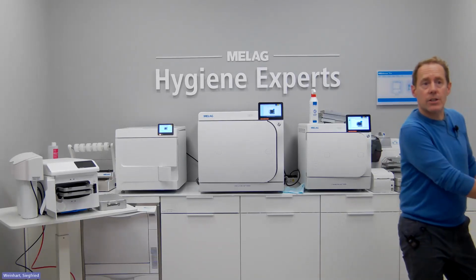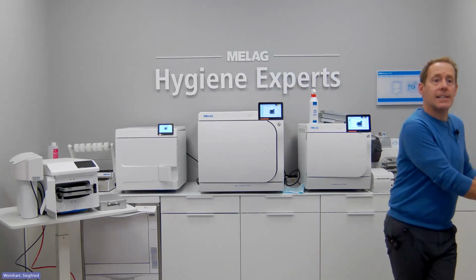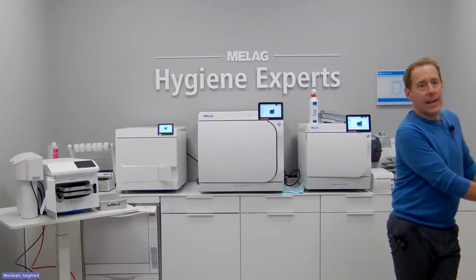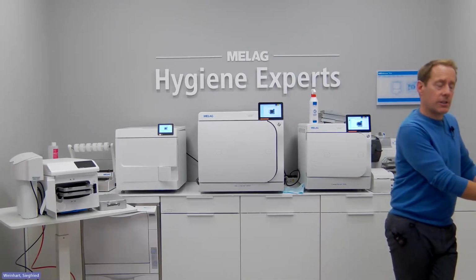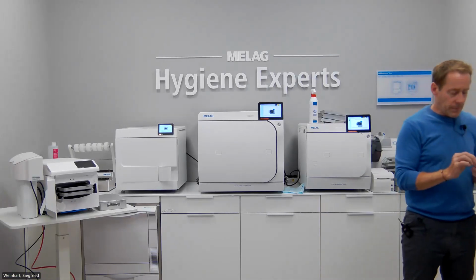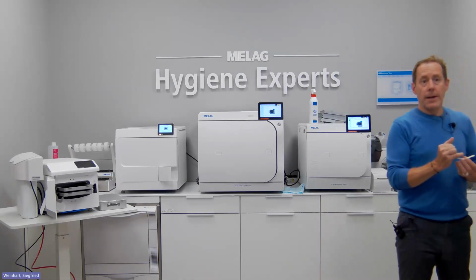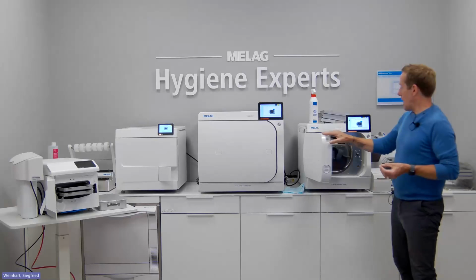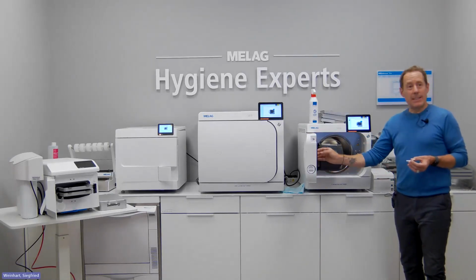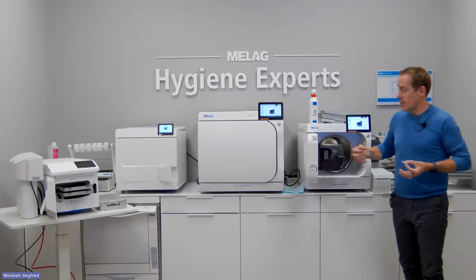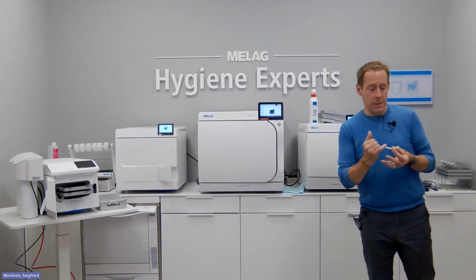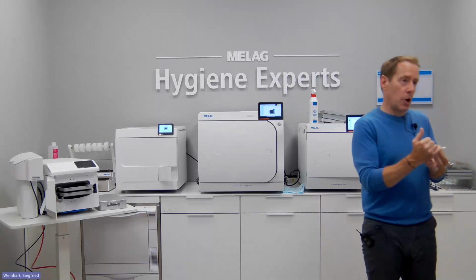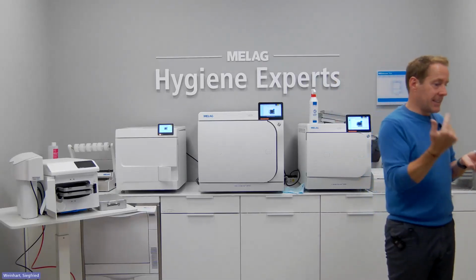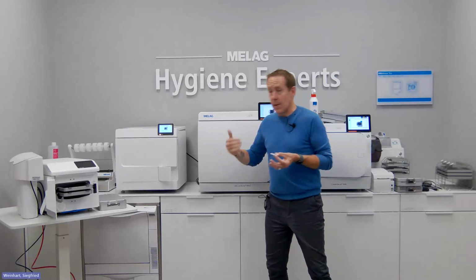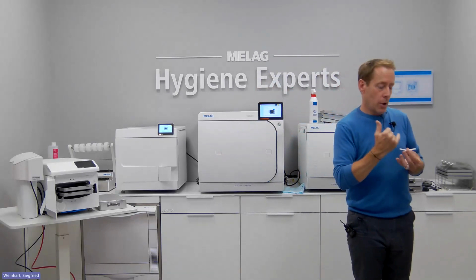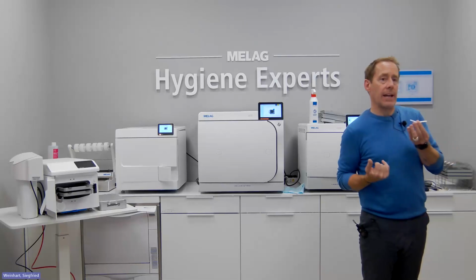If a helix doesn't change color completely, but does change partially, is that okay? No, it's got to change completely. If only slight parts of it are changing, that could be indicative of a problem - it may well be that your door gasket needs changing, as simple as that. It might not be able to pull the vacuum properly, because if it's not changing completely, that could mean there's still some air in the helix itself, which inhibits the steam getting there. You should get a complete change on the helix.